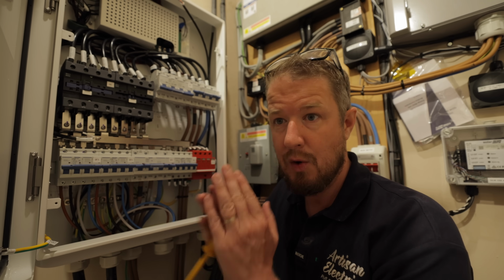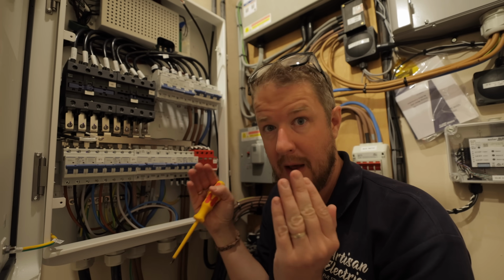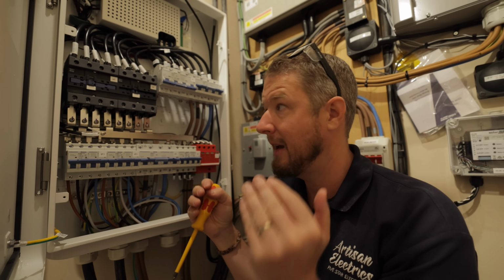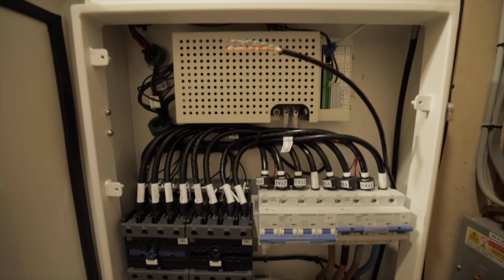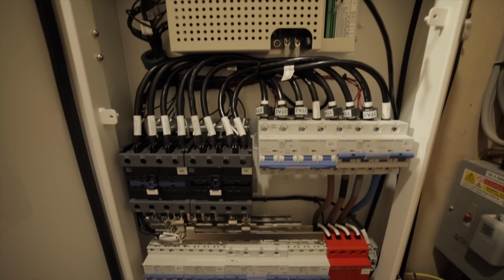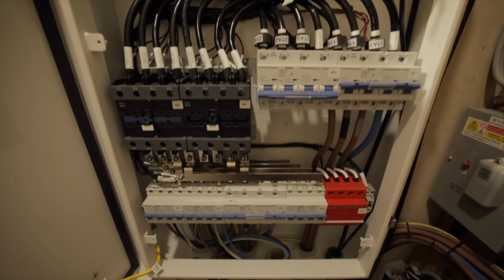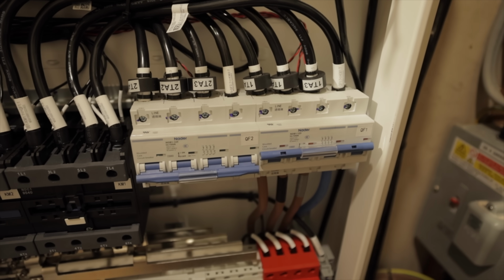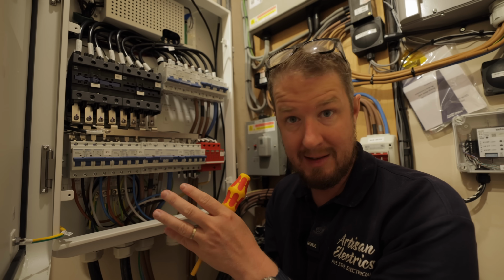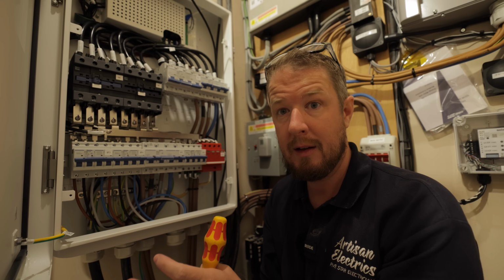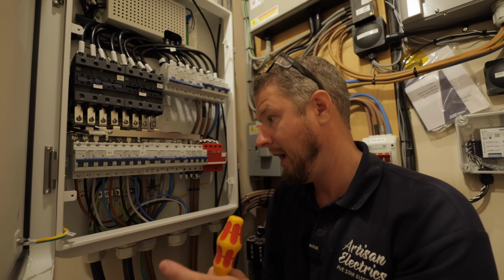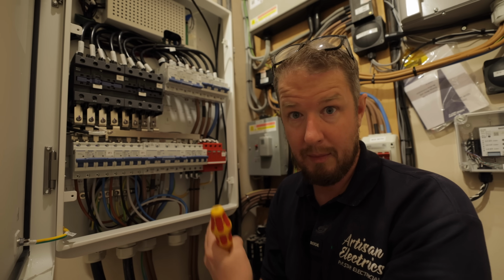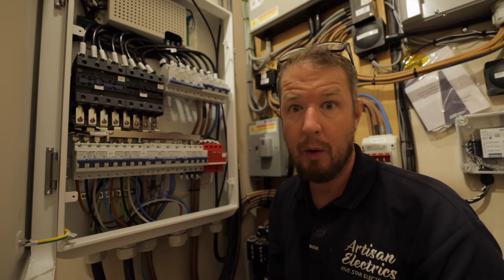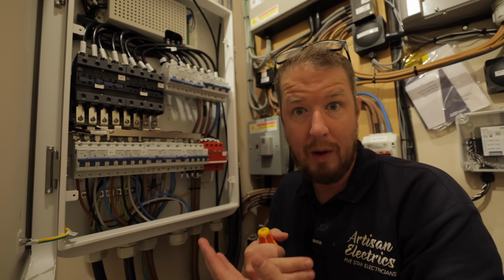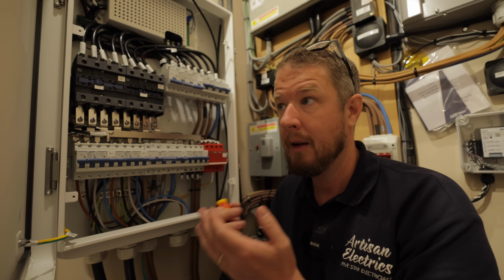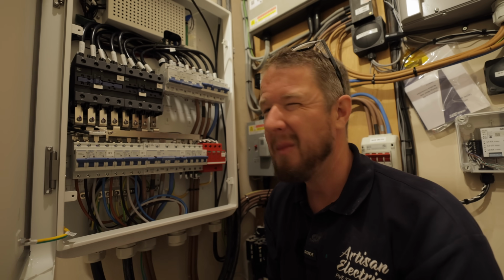So it's for that reason you need this separation and this automatic off-grid setup with the relays. And what it also does, it has a neutral earth bond relay where it basically clamps the neutral and earth together, and then it will use our backup earth that we've fitted, our earth rod, as the earthing facility for the property, so that again, if the main earth from the supply is down, we've still got a local earth, because they could have potentially cut the whole cable with the neutral and earth in it, feeding the property, and we would have no earth. So I hope that all makes sense.